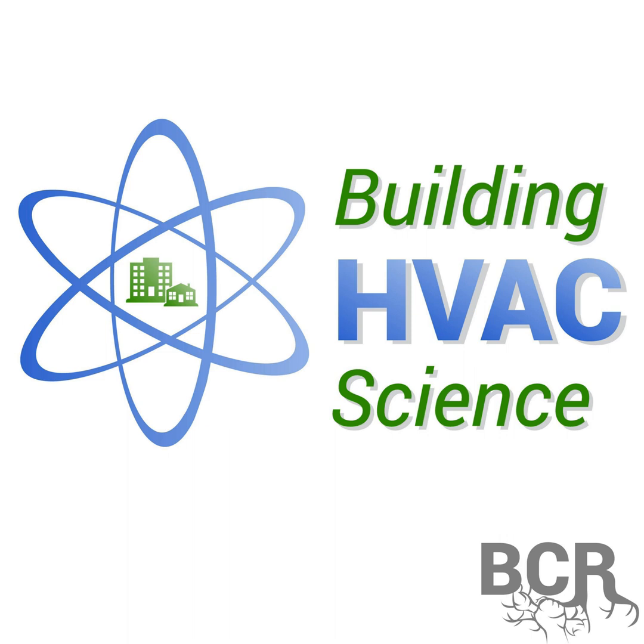And the other part that's super inexpensive is the filter grille itself. It's a $25 product, maybe a $30 product in the 20 by 20 or 24 by 24 size with the 2-inch deep thickness. So on each of these systems, for, let's call it, a price upgrade of at the most $50, we're able to deliver really top of the line filtration. In our minds, we're working through different options for a future scenario where we think a customer at some point is going to ask us for maybe MERV 16 filtration or maybe HEPA level filtration, and thinking through how we can do that with a return filter grille, or how we would go about doing that? That's the next step. We're waiting for that client to come across our desks.